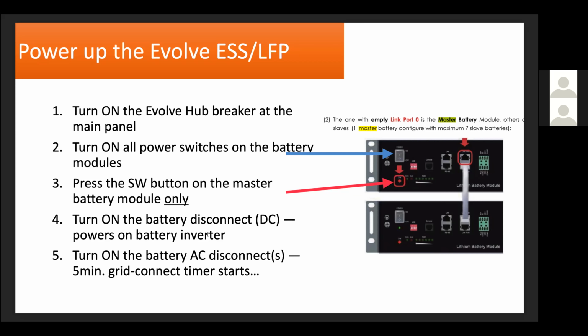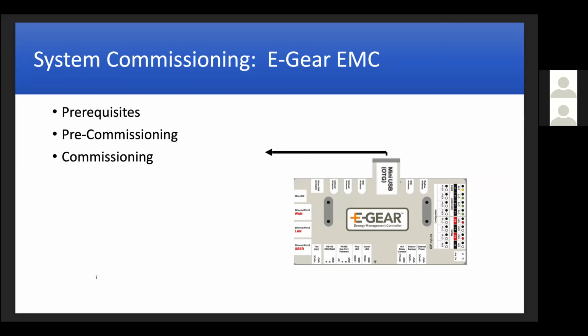Once that's powered on from the DC, then you turn on the battery AC disconnects, and a 5-minute grid connect timer starts up. Standard IEEE 1547 5-minute timer. Once that has elapsed and the grid voltage is within specs, the front panel of the PCS will have a solid blue light saying that it's in grid connected or gate block mode. At that point, then you would proceed to system commissioning.